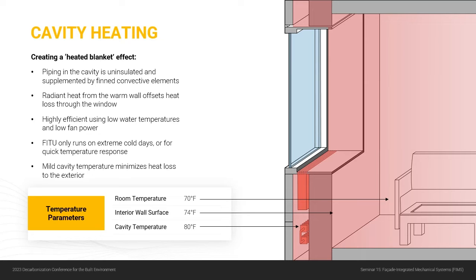Now what this does is we're heating the cavity. That heat will conduct through the uninsulated or poorly insulated existing wall and essentially radiate into the space, creating a radiant wall effect. So obviously a very comfortable way to heat a building, also very efficient because we can do it with very low water temperatures and there's no fan power involved with that. Once you have that heated wall, the only heat loss from the space is through the window. So you just need enough heat from that wall to offset your loss through the window. And this is a new window. It should be a high performance window, so we're not talking about a lot of heat loss here.